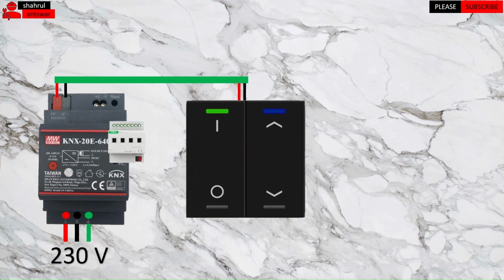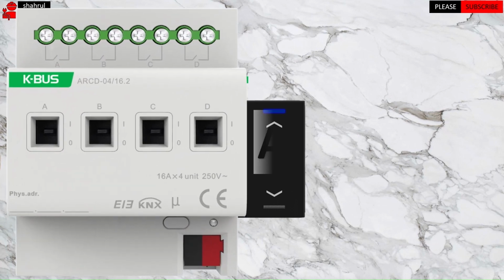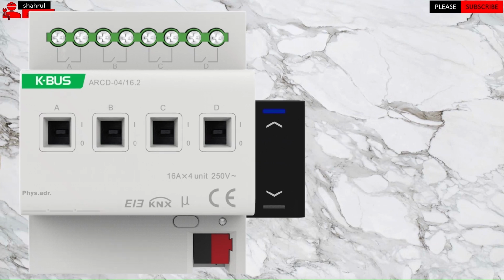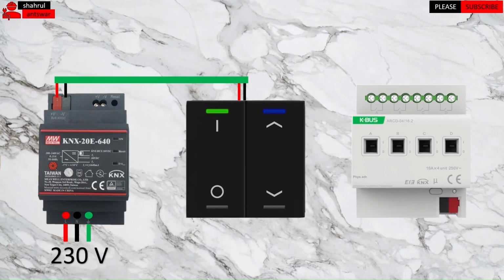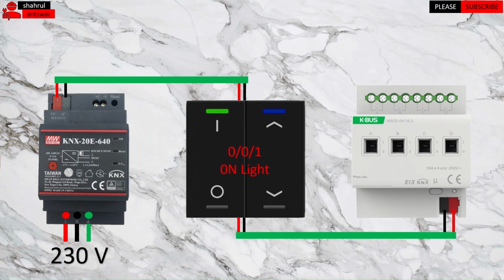The third device required in the system is the actuator. There are various types of actuators, and the one shown is a switching actuator. Just like the sensor, the actuator is also supplied with 30 volts DC via a bus cable. The actuator will be turned on with this voltage. The actuator will receive the telegram or signal sent by the sensor. Next, the actuator will perform the action, like switching the light.